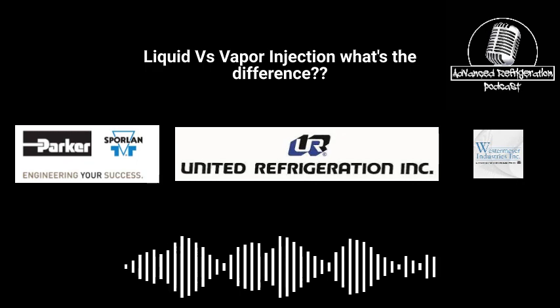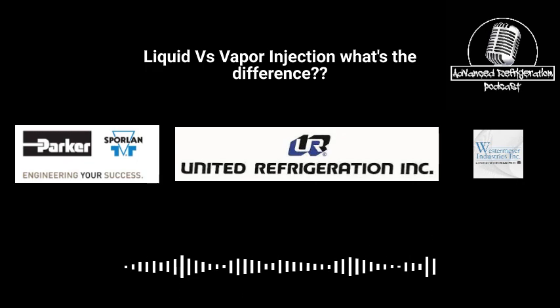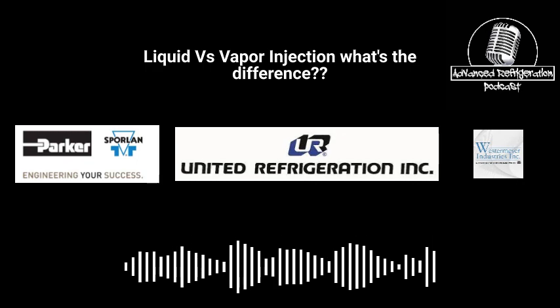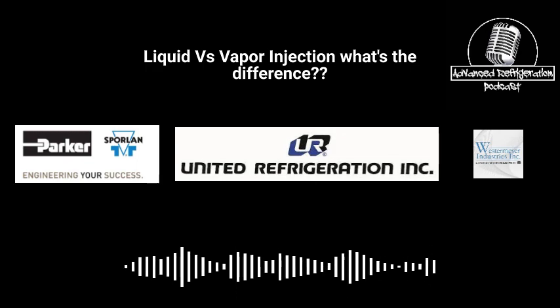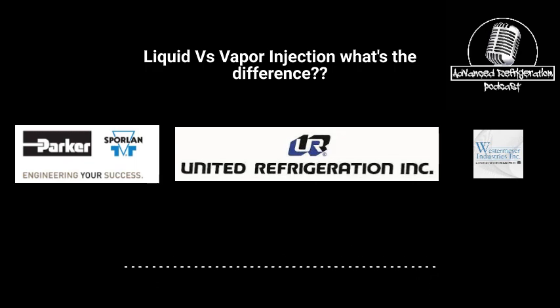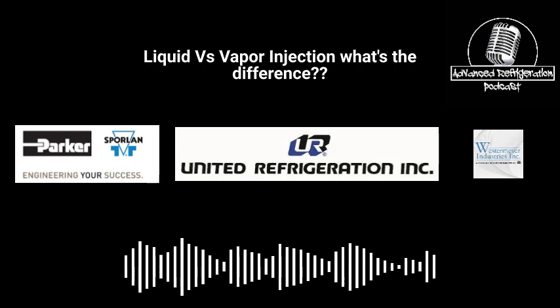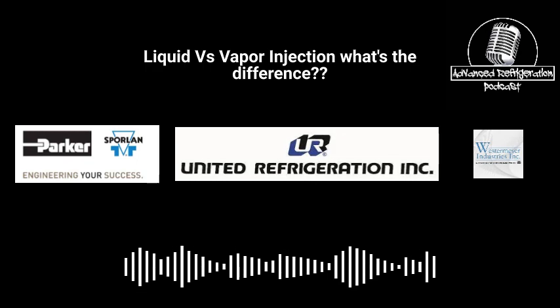But if the suction looks good, it's probably coming down the vapor line. Generally, it's a bad sensor on a subcooler controller, or it's something else. Like somebody changed the sensor or changed the transducer type and never changed it in the controller. That's a common one. Oh, don't be fooled by the Sporlan subcooler superheat controllers. They have an adjustment in there for whether it's looking at atmospheric or gauge pressure.